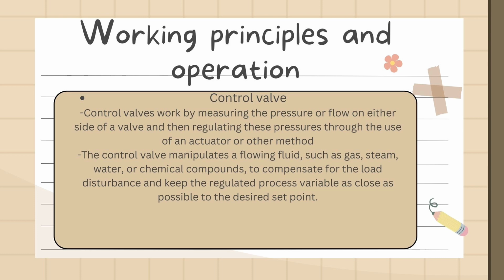The control valves work by measuring the pressure or flow on either side of a valve and then regulating these pressures through the use of an actuator or other method. This control valve also manipulates a flowing fluid such as gas, steam, water or chemical compounds to compensate for the load disturbance and keep the regulated process variable as close as possible to the desired set point.